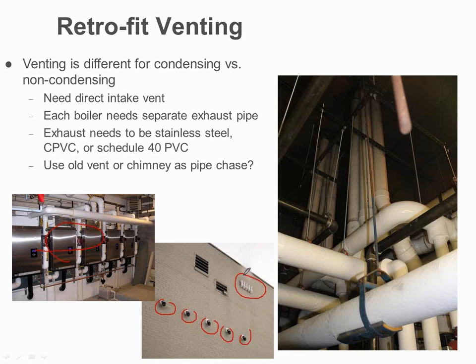Sometimes on buildings, if we can't get out the sidewall like we did over on this side, we'll actually go up the old chimney. We'll use your old chimney or your old exhaust stack as a pipe chase for all of our new PVC piping. Right, we already have the hole there. It's already running up 2-3 stories. Why not go ahead and use that, right? We'll have dedicated PVC pipes, but we'll use the old exhaust pipe as a chase for all these new ones.